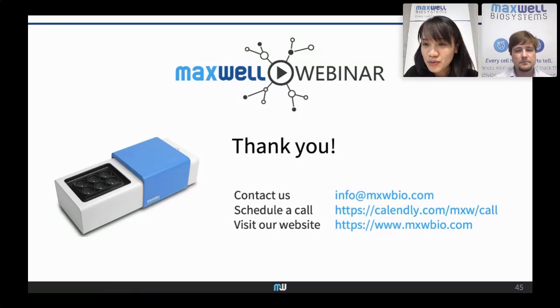Okay, and I think we have our last question here. There have already been multiple works using microelectrode arrays for retinal studies. What is the advantage of MaxOne for doing retinal research? The advantage of MaxOne is truly the high density, because the center to center distance between two electrodes is only 17.5 microns. So the real advantages come when you're trying to look at the receptive field of the cells, meaning you can define these much more clearly. And the other advantage is that when you perform spike sorting on the retina data, which you have to do, it's much easier to separate clusters because you see the signal from one cell on multiple electrodes. So then you can have much clearer data.